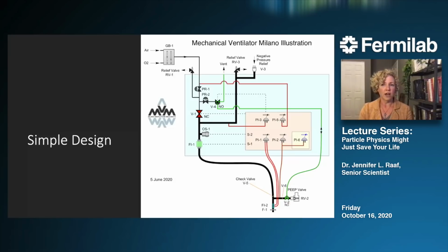After mixing the air and oxygen, it goes into the ventilator, and the ventilator is attached to the patient at the very bottom of this image. So you can imagine a patient mouth there just below the thing labeled F1. Inside the ventilator, the dashed lines that you see are all electrical connections, and the solid lines are all gas connections. If you follow the black path, that's the breathing path, and you'll see some side branches; those are safety features. You'll also notice there are just a few valves and pressure regulators in the design. Those are all labeled with PR or V and a number. That was in keeping with our design principle of minimizing the number of parts.